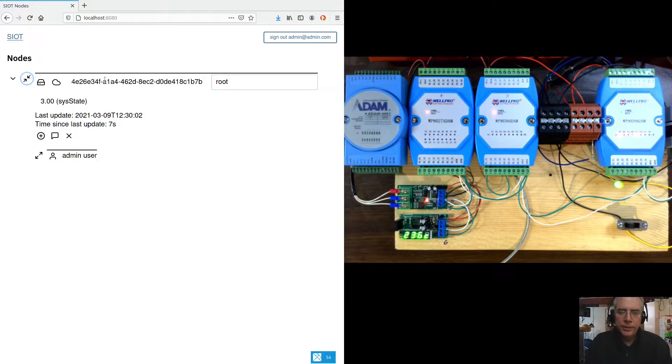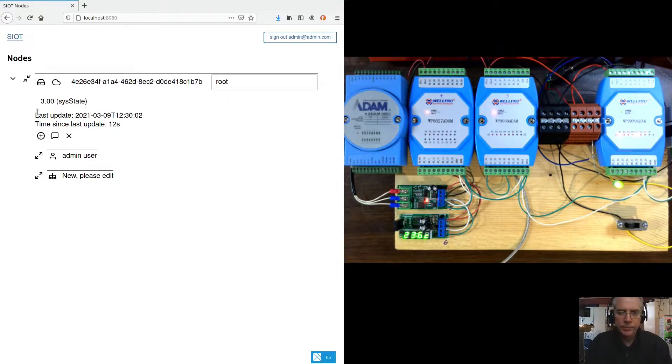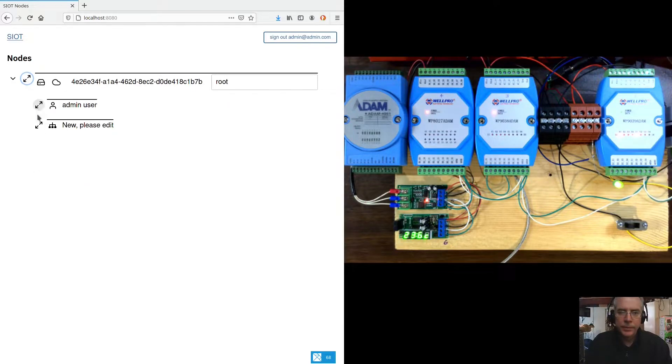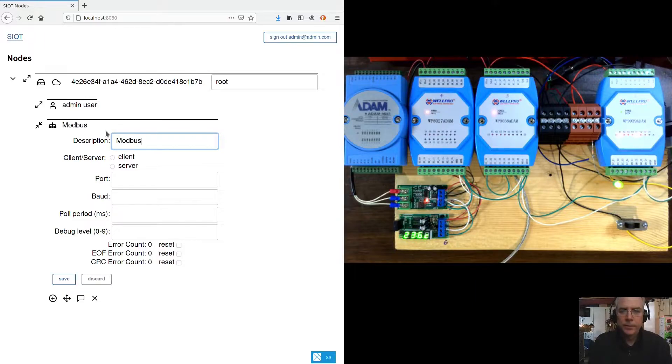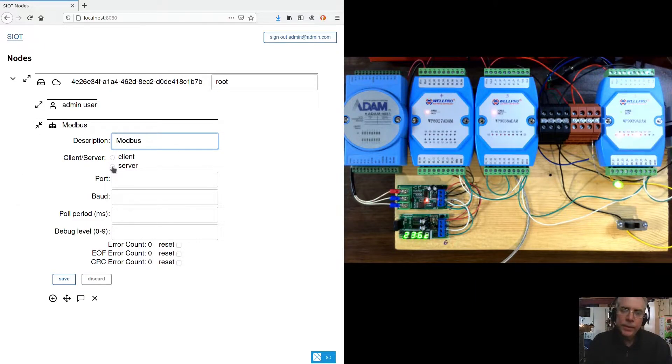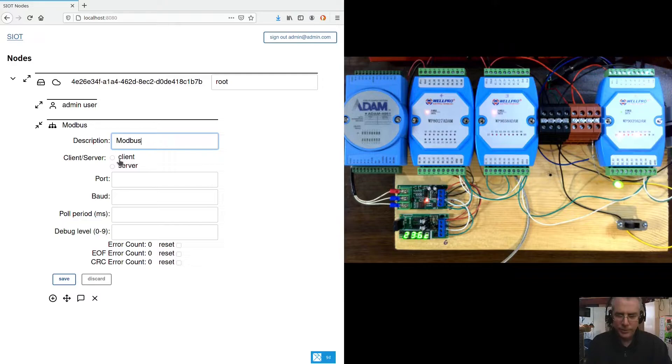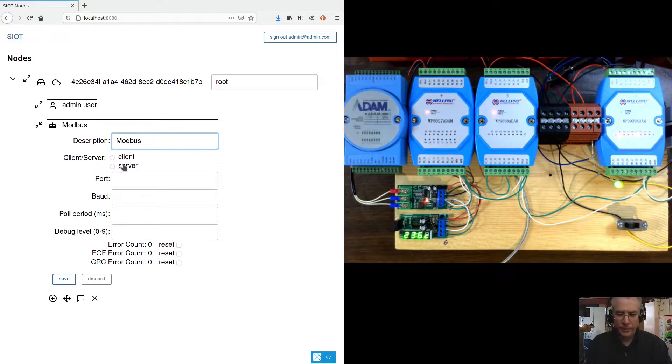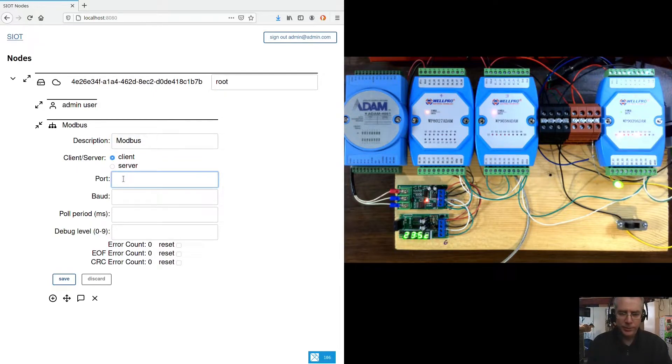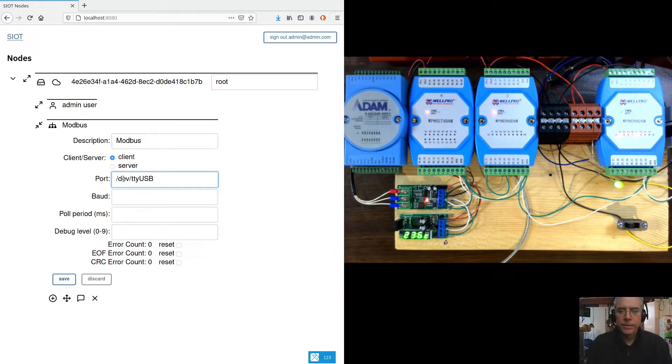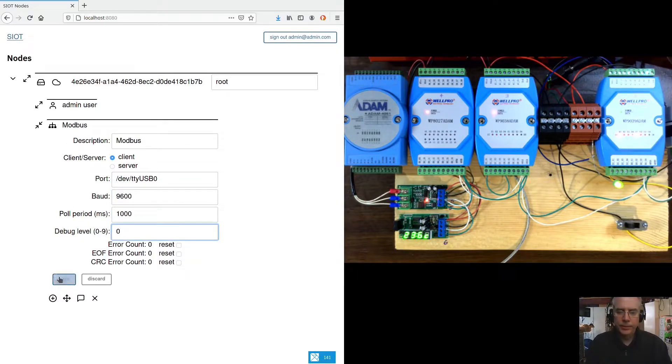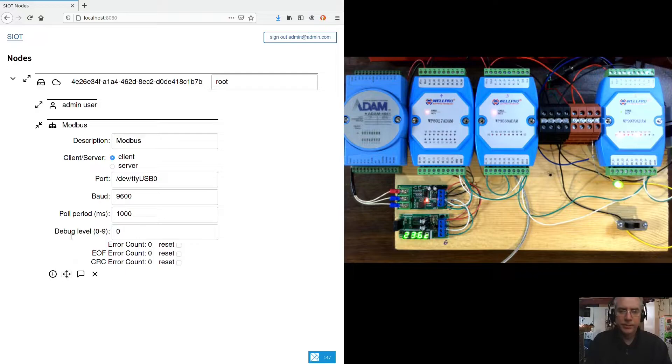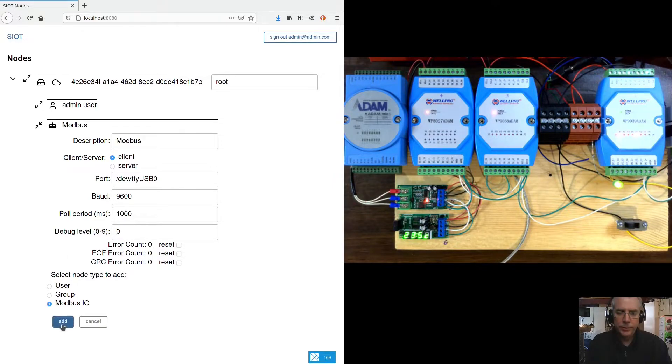So if we expand the root details, we can add a Modbus. Modbus uses client and server a little differently than one may think. The client is actually the device, the master device on the bus. And the server is actually the device that you're reading. So we're going to configure this instance as a client. 9600 baud. We'll poll it once a second and set the debug level. Now that we have a bus defined, we can add IOs to this bus.